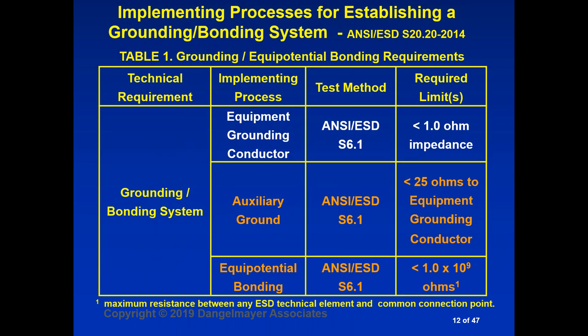So this is a chart that you'll find in S20.20. It talks about the requirements for various grounding methods. We're only talking about the principal one where you use the equipment grounding conductor that's specified in S6.1. And the required limit is that you have less than 1.0 ohm impedance from your grounding point to the electrical ground. Other grounding methods will have different requirements in terms of resistance, but this is the primary one that's in use.